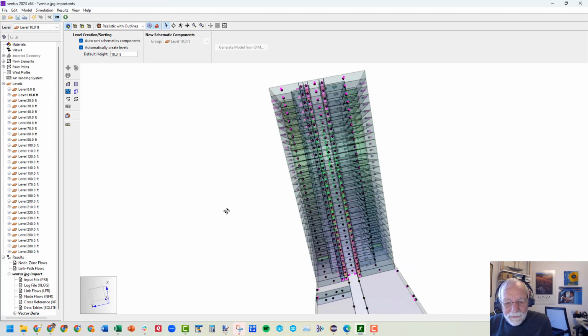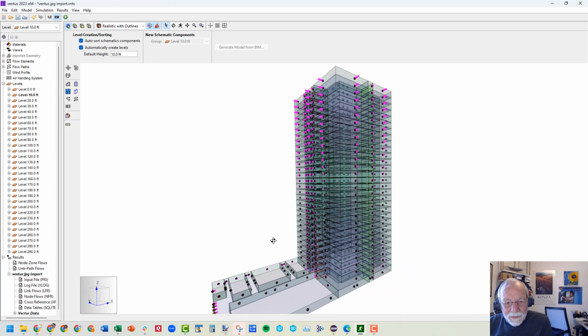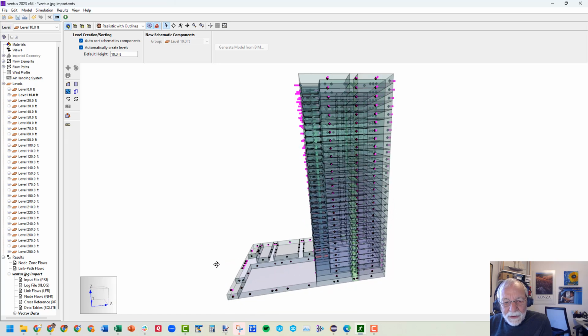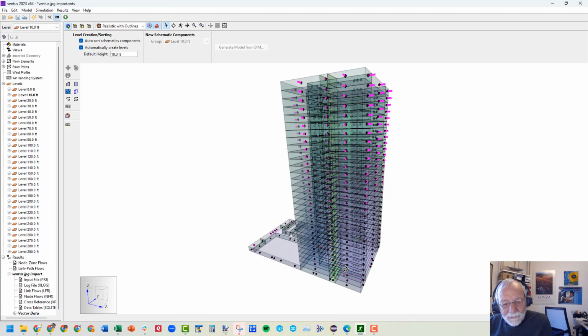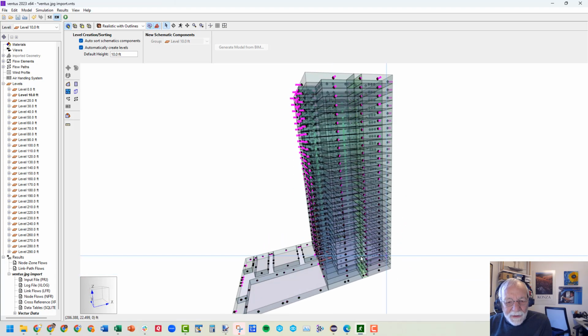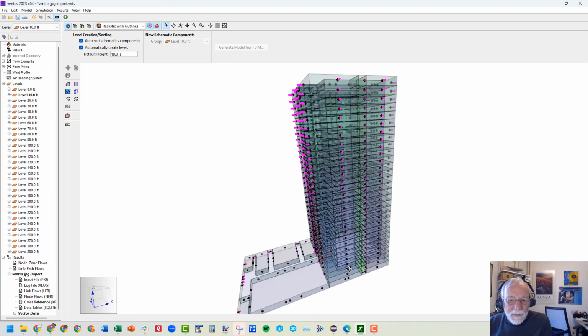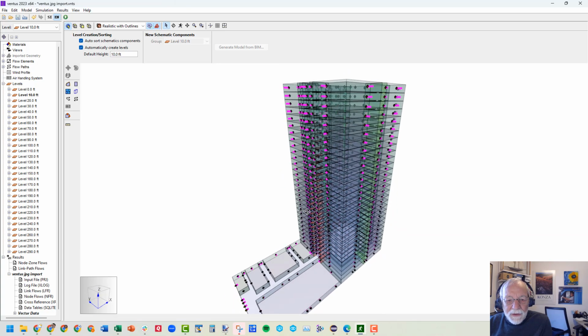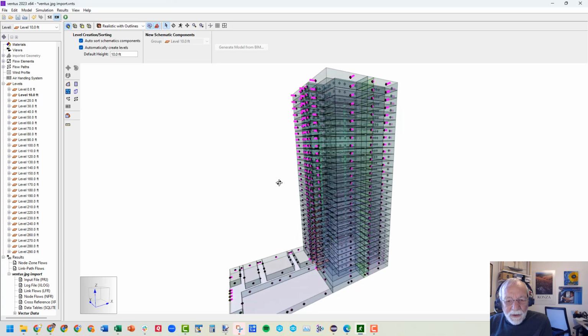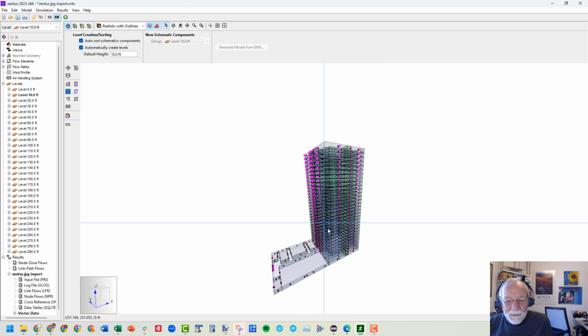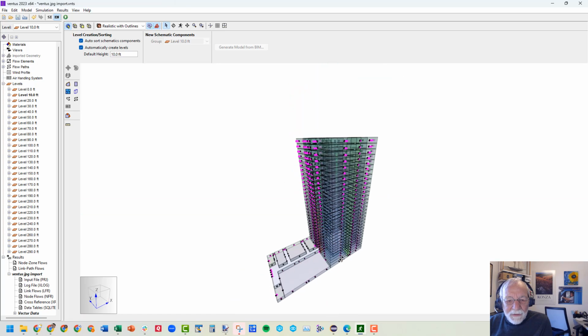We have the correct kind of winter condition where we have the flow out at the top and flow in at the bottom. I'll have to compare to a contam model that I make independently to really be comfortable with those results. But there we are. It looks good. I have to do some checking, but I think we have a good start.